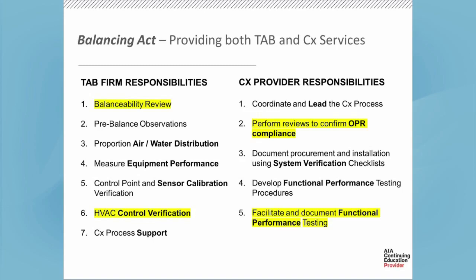Obviously the commissioning provider has to do document procurement and system verification checklists. They develop the functional performance testing procedures, and ultimately facilitate and document the functional performance testing. You could argue that step is redundant with the HVAC control verification step under the tab firm's responsibilities. We're going to talk about how you distinguish those roles if the tab firm is responsible for full control verification, and the commissioning provider is performing functional performance testing.